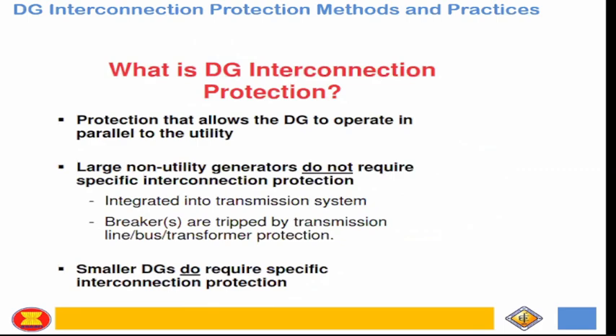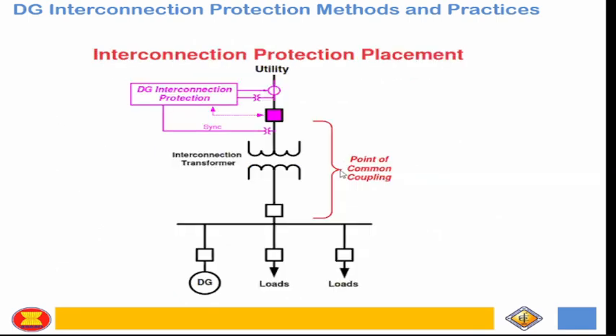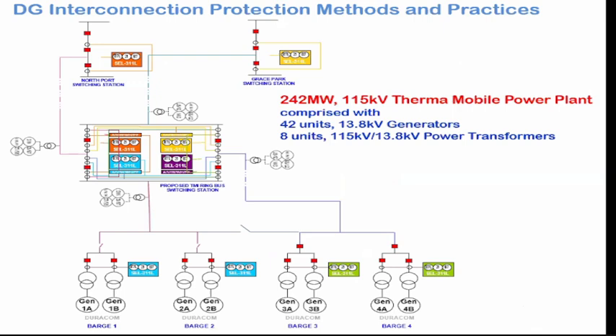Okay? So, what is DG protection? It is protection that allows the DG to operate in parallel with the utility. The protection arrangement is usually on the high side, on the utility side. And then there is DG interconnection protection at the interconnection point. So this is one of my experiences.